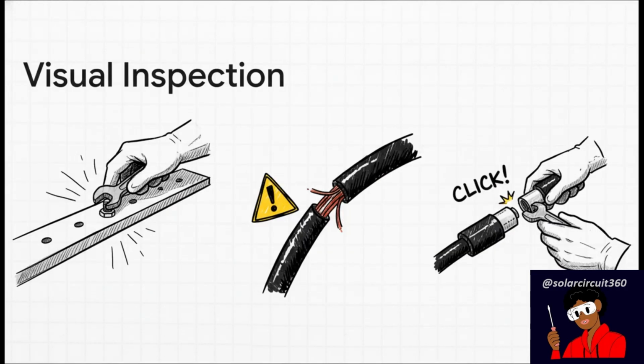Okay, first up, the visual inspection. This means getting your eyes and your hands on everything. Are all the cable connections on your bus bars and terminals actually tight? Give them a little wiggle. A loose connection isn't just a bad connection, it's a fire waiting to happen. Look for any exposed wires, any little nicks or crushed bits of insulation. And those MC4 connectors from your panels, you should hear a solid click when they lock. If you don't hear that click, it's not secure.